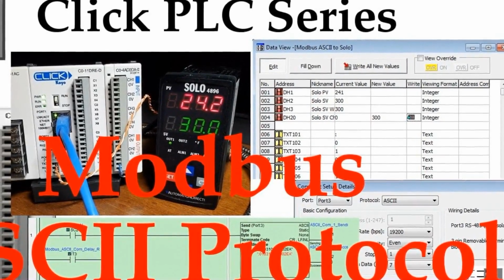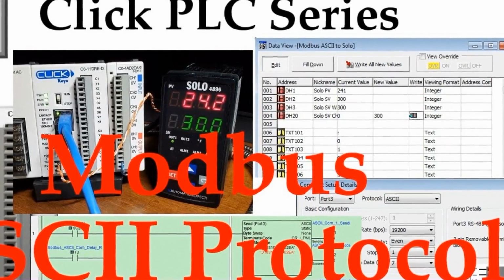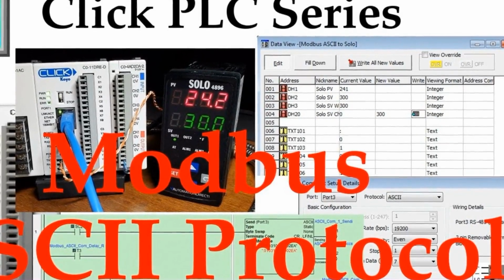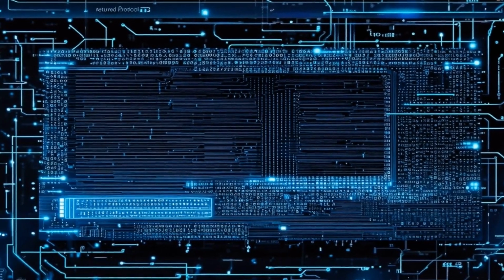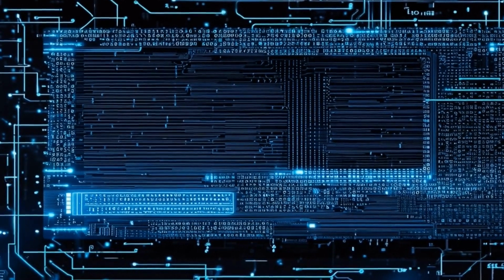Using the Click programming software, call up Comm port setup from the main menu and select Setup under port 3. Choose ASCII for the protocol and match the communication parameters to those of the Solo controller: 19,200 baud, even parity, 7 data bits, and 1 stop bit.